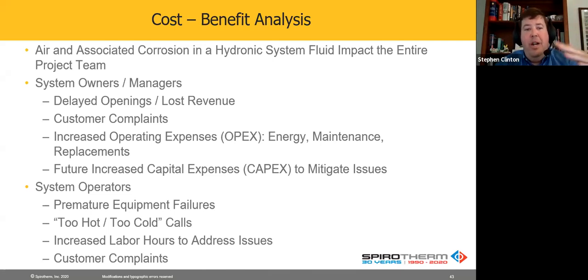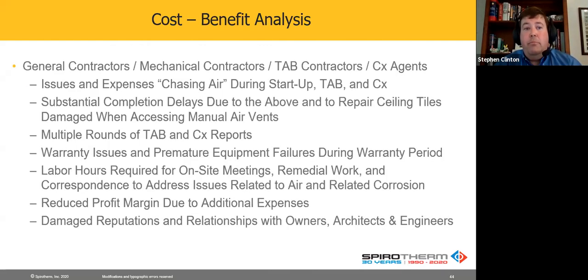You have air in the system, you're trying to chase it down. You've got people that are dedicated, those two guys, all they do is chase problems. And they're dealing with customer complaints as well. When you get into the contracting side, contractors, the generals, the mechanicals, the test and balance guys, and commissioning agents, you're chasing air. You're trying to get that stuff bled out. You're getting inaccuracy in some readings. You're getting headaches. Everybody gets at each other's throats sometimes.